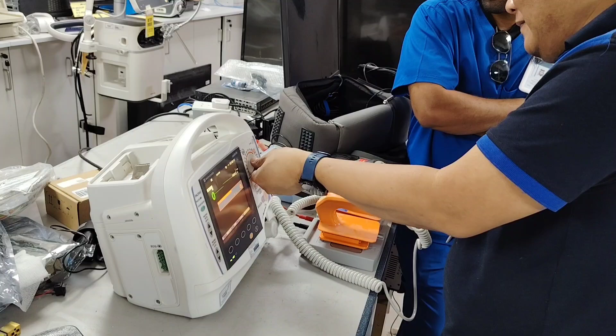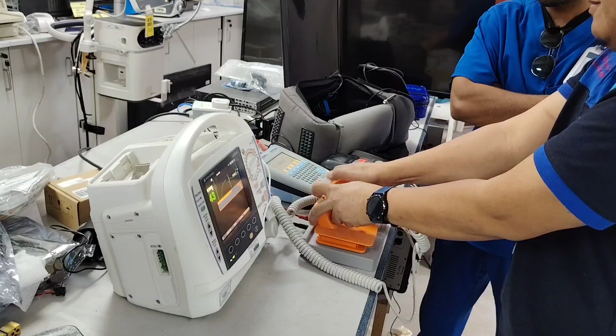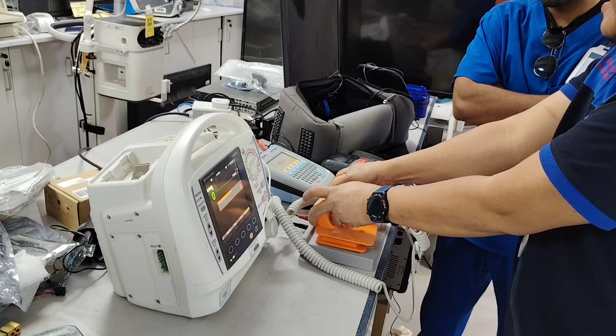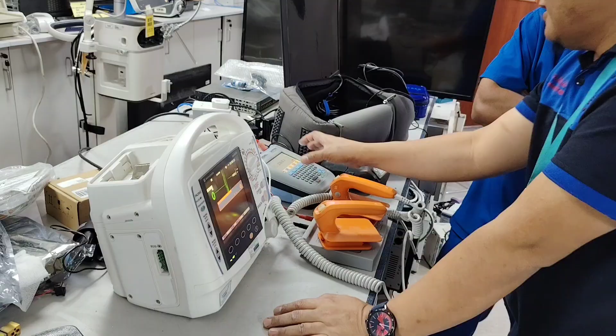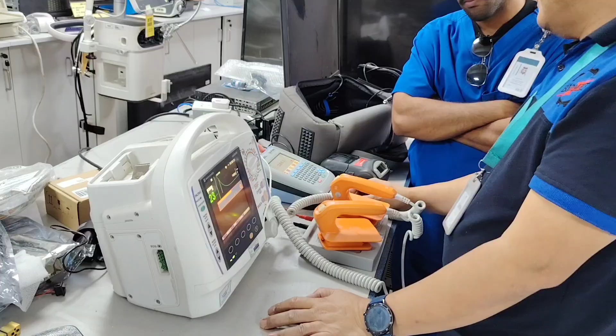So at 270, you count the charging time, because there is a limit for the maximum 270: the charging time should not be more than 10 seconds. 1, 2, 3, 4, 5. It still reaches the 10 seconds time. So our 270 output is 239 only. Very low. There is also a factor for this.